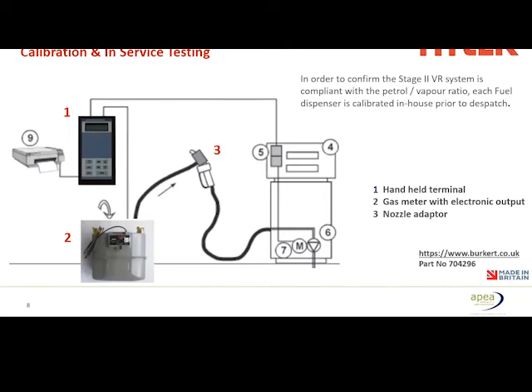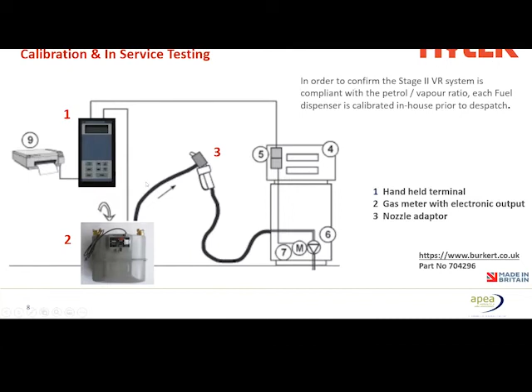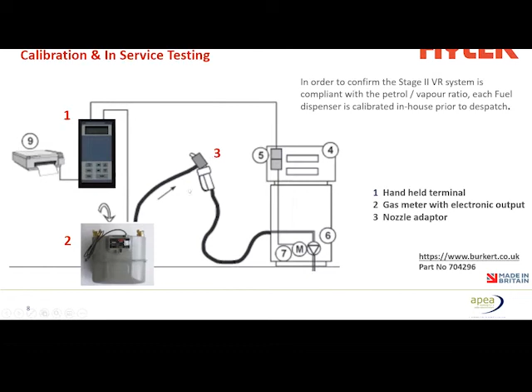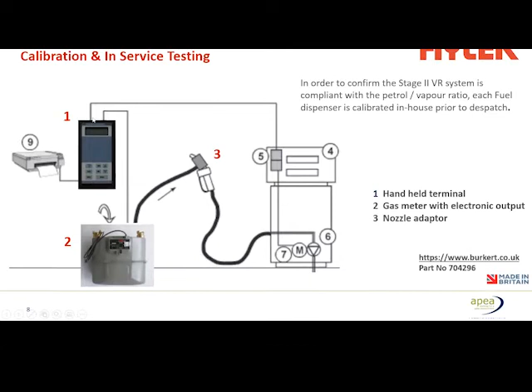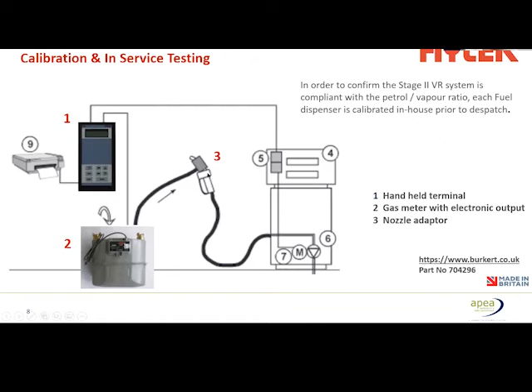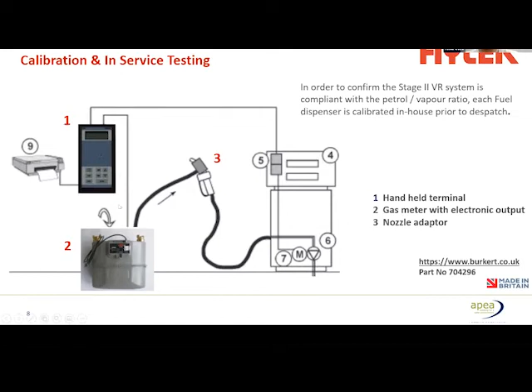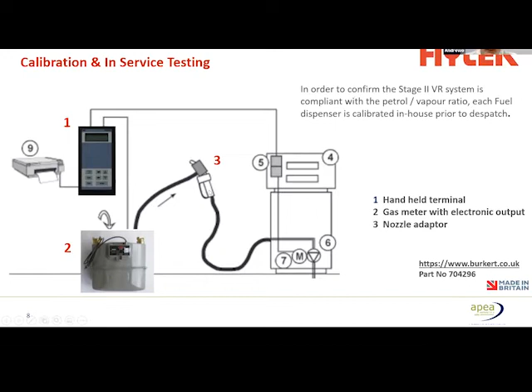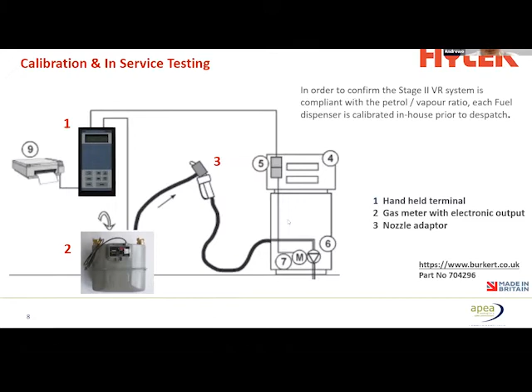In order to ensure that we are compliant with the 85% plus, we need to calibrate it. And in order to do that, there are 3 main components here. There's an adapter that goes across the end of the nozzle. We have a gas meter here, which has an electronic output to a handheld terminal. So in order to calibrate, we are dispensing fuel through the nozzle, through the adapter, the vacuum pump is drawing air in through the gas meter, and we've then got an output coming to our handheld terminal. So by using that setup, if we're not meeting the 85% requirement, we can go into the nozzle, adjust the proportional valve, and that will then achieve the correct tolerance.